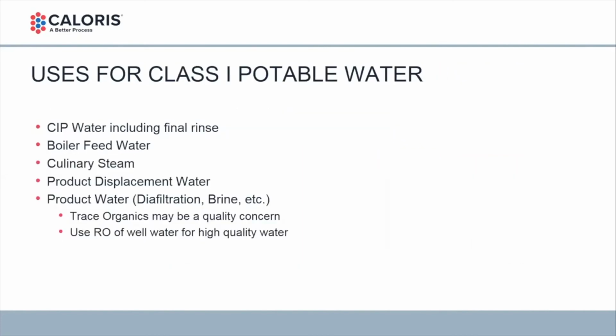Okay, last slide. What are the uses for Class 1 potable water? Probably the biggest use I'm aware of is CIP water for cleaning your equipment, including the final rinse. It can be used for boiler feed water. It could be used for culinary steam. It can be used for product displacement water at the end of a run. It can even be used for product water, diafiltration, brine, etc.